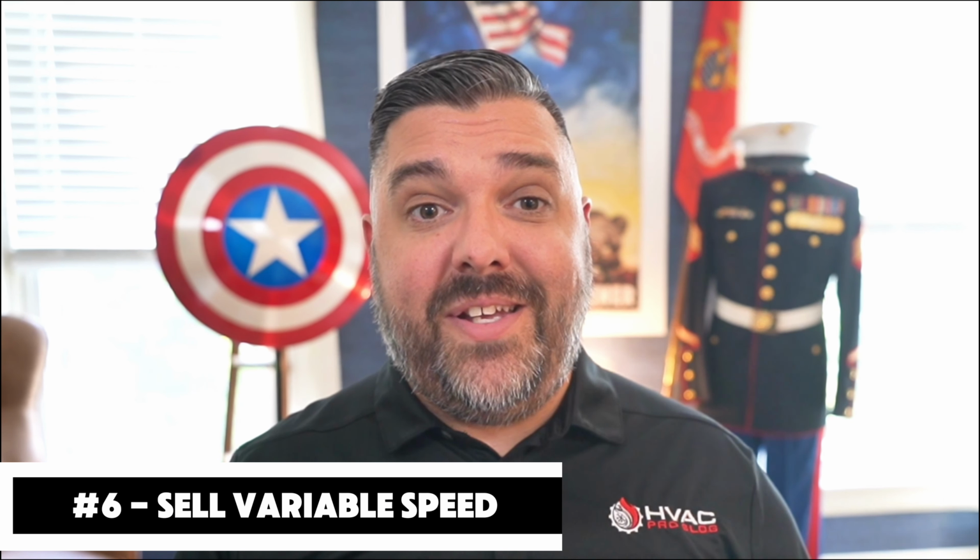Now, there's one more big thing that separates pros from everyone else. Good contractors do Manual J calculations. Great contractors sell variable capacity equipment and understand how it changes the sizing game. Here's what most contractors don't get about variable capacity systems. Yes, they can modulate down, but they don't magically solve oversizing problems. A variable speed heat pump might ramp down to 40 or 50% capacity at some conditions, not 1 BTU per hour. You still need accurate load calcs, but here's where variable capacity gives you an edge.